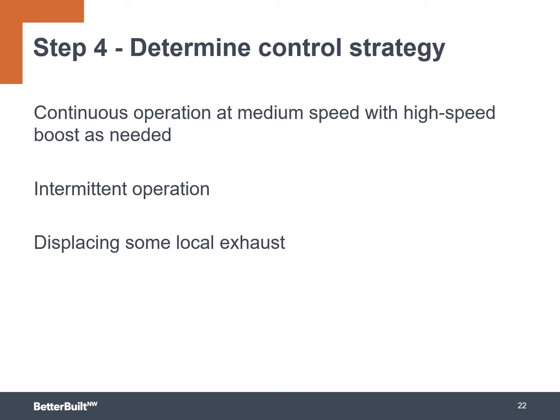By displace local exhaust, I think we're going to talk a little bit more about that later, but effectively, if you're constantly removing, let's say, 15 CFM out of a bathroom, the Washington State Mechanical Code has a prescriptive number that you need to meet for what they refer to as local exhaust. So you could subtract 15 CFM off of that number, and that typically means you can get a slightly smaller fan installed. So instead of having to buy a 90 CFM local exhaust fan, you could potentially buy a 70 CFM.